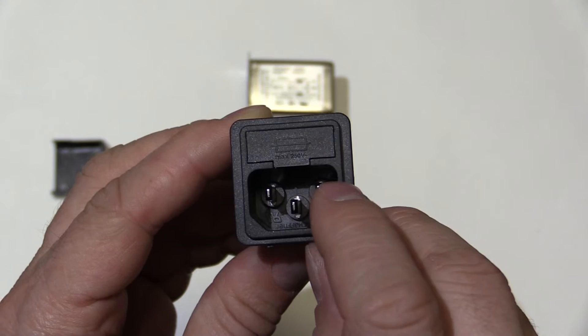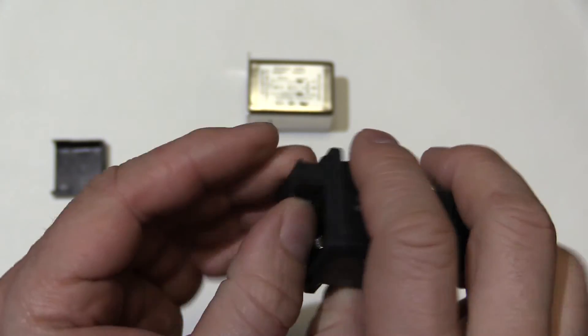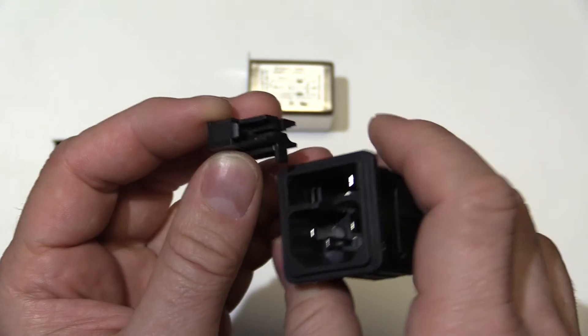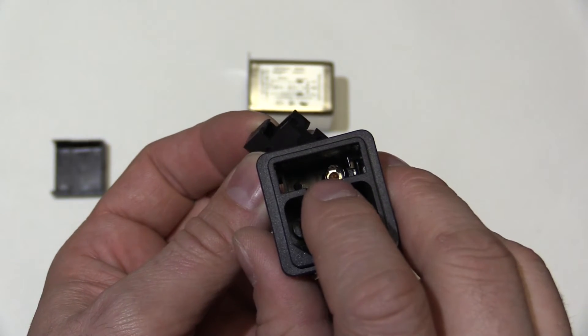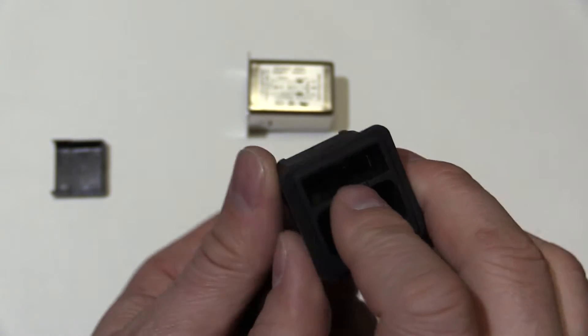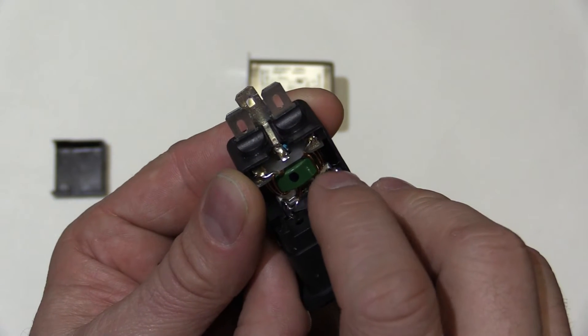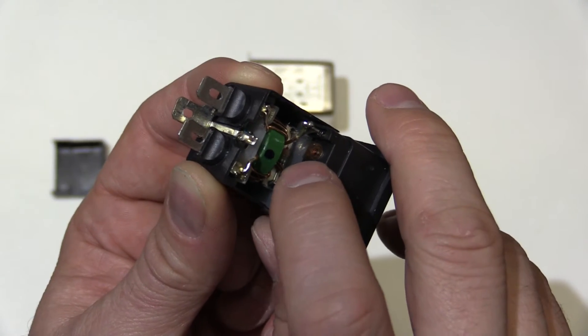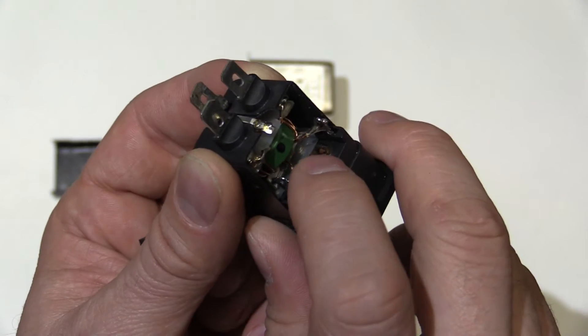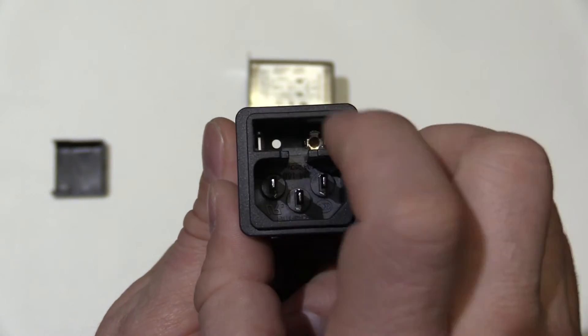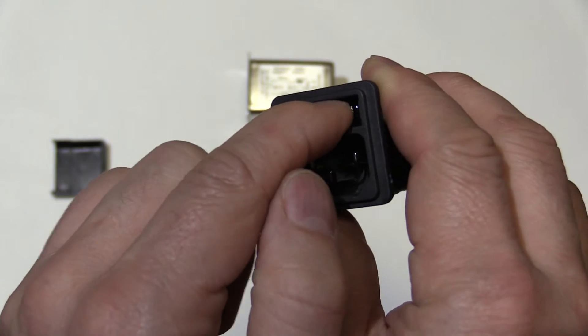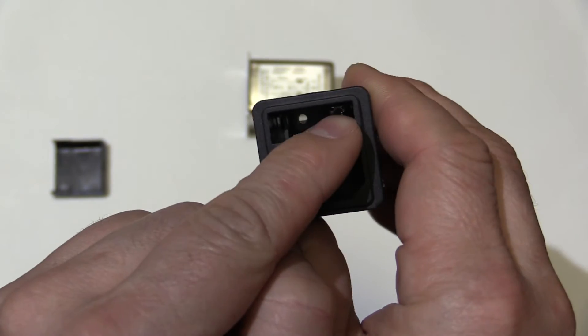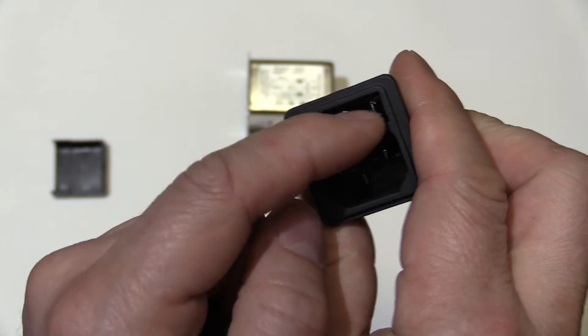Your voltage comes in on this pin, and then we've got a fuse holder. We take that out. The fuse sits in here, and you can see the back there where the voltage comes through. It's connected onto the inside there, just near where my finger is. That's a nice feature where if you pull this out, you can't get your finger in to touch the live terminal, because the one you can reach is the load side. So that's never going to be live without a connection through to the back.